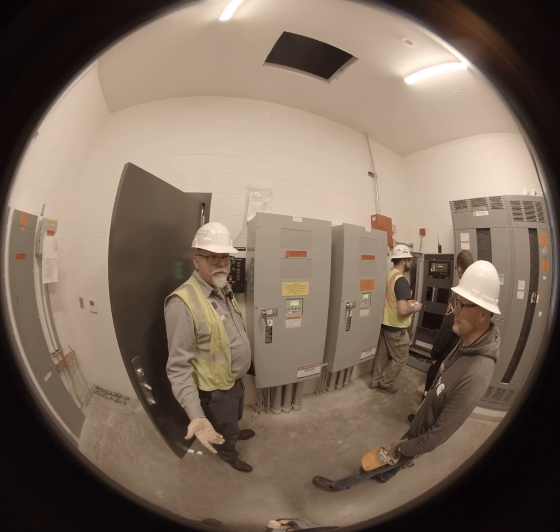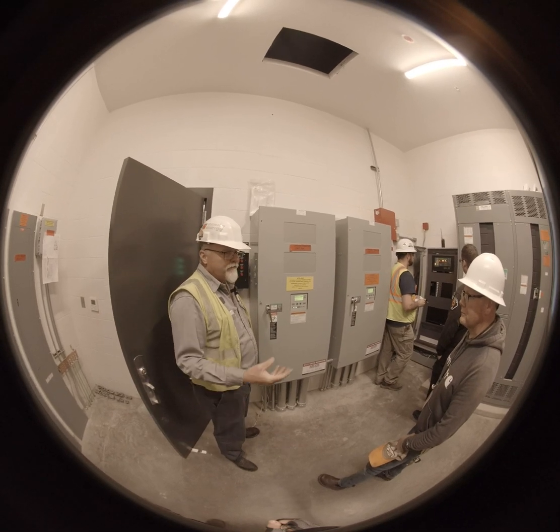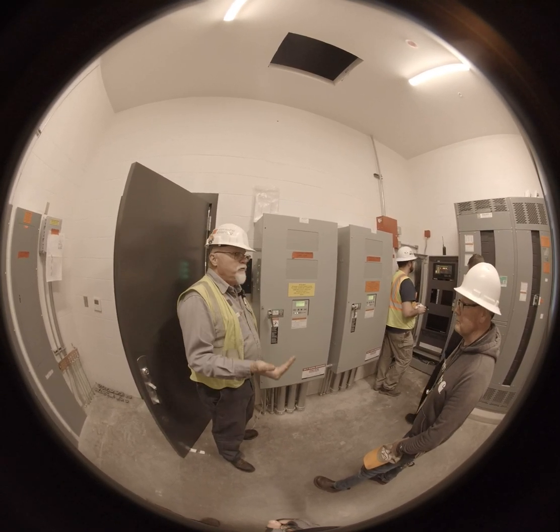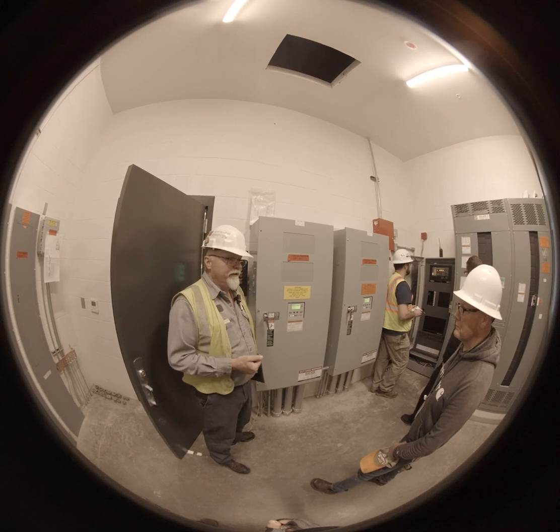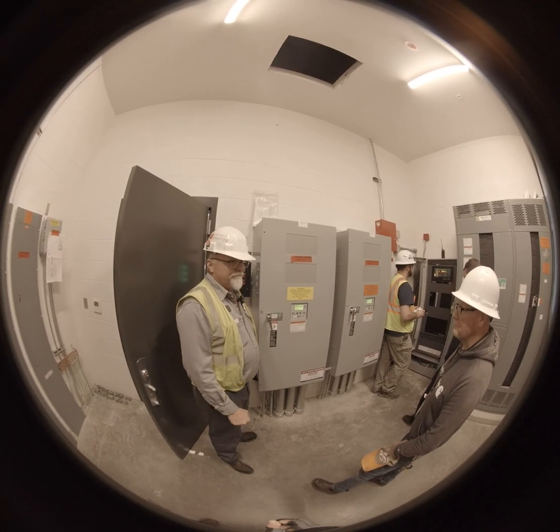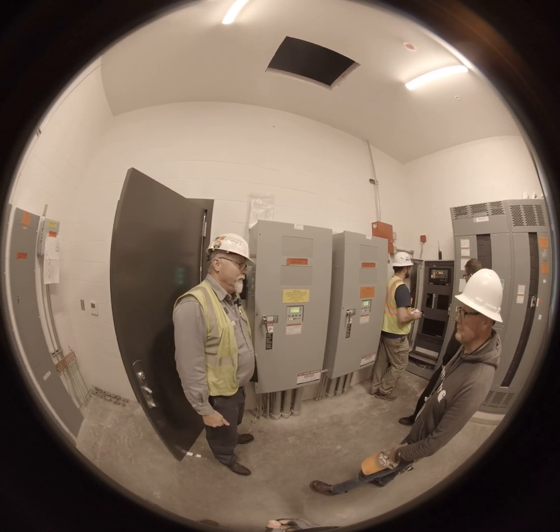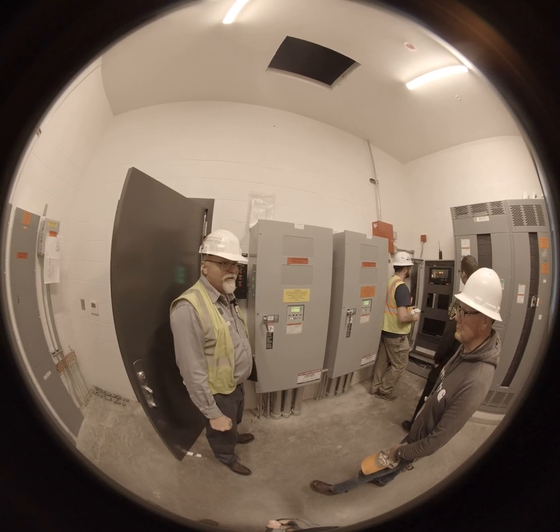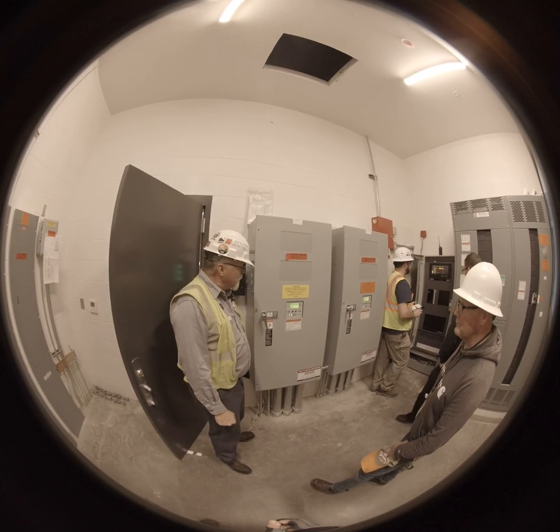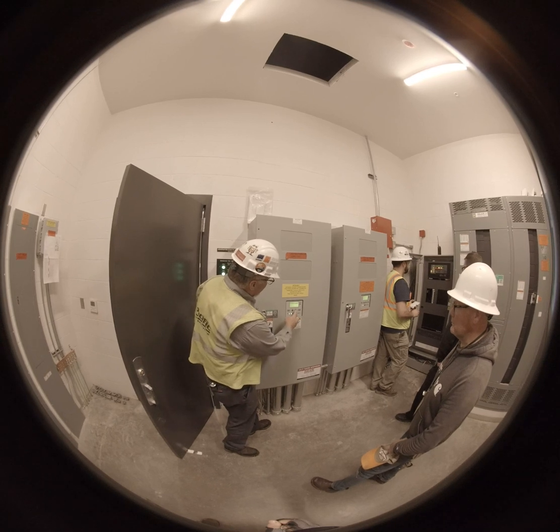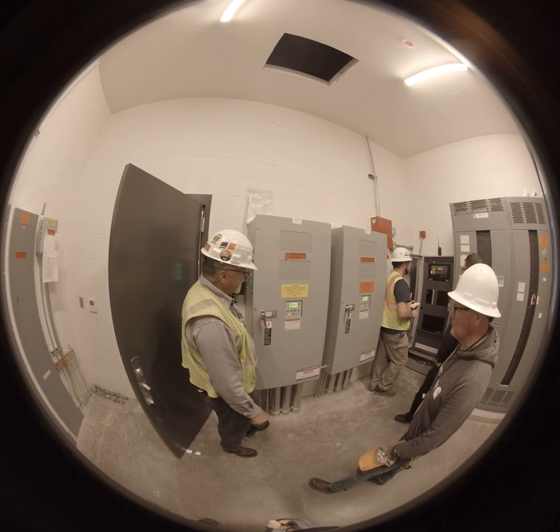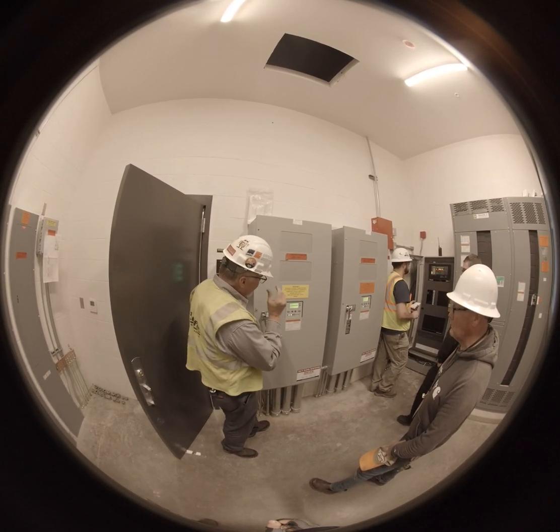And that mainly applies to the big bore engines, because they actually have timers set up in those, where if you do not exercise them at least every 28 days, it brings up a pre-alarm. Because you've got an engine that's worth, you know, $250,000, they don't want it to wipe out bearings. So we're going to go down one. Timers. So I talked about the time delays on these.